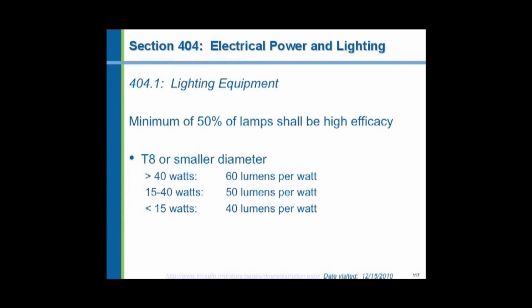Now, the lumens per watt, this is the amount of light that the lamp puts out for every watt of power input. 60 lumens per watt at 40 watt lamps and larger is typical of normal fluorescent lights. However, to get that, you have to calculate the ballast along with the lamp. Now, it used to be that magnetic ballasts used 20% more energy in addition to the light. So a 40 watt lamp would use 8 additional watts in the ballast. We'd lose that heat. It'd go off into the air conditioning system.